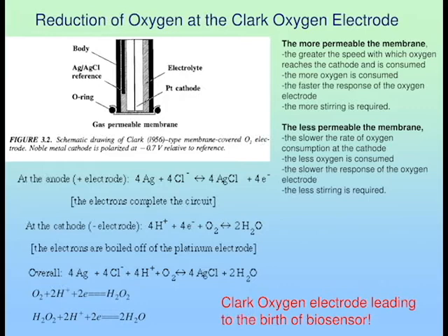the which electrode? Farhan? Reduction at which electrode? Platinum or AgCl? Platinum, that's correct. That's the working electrode. Take note, it's a gas permeable membrane. If the membrane is very porous, when I say porous, this is relative. For our naked eye, we cannot see the pores, but of course the manufacturer can tell you what the pore size is, how many pores there are.